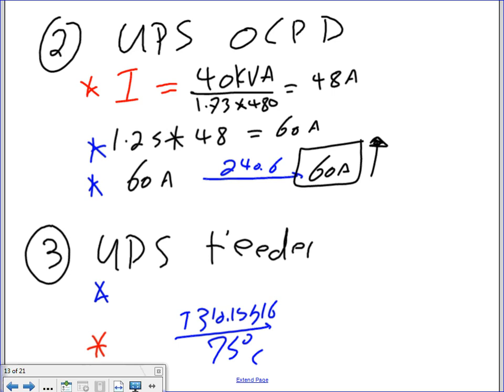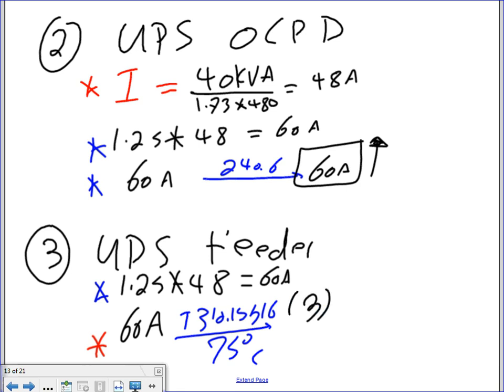Let's go to the feeder, shall we? So that's the UPS overcurrent device. Now the UPS feeder. Adam, it's identical to the overcurrent device, the same calculation, guys. You take 1.25 multiplied by the full load current, which is 48. We already did this one. End up with 60 amps. Take your 60 amps to 310.16, 75-degree column, and that will get you 3 conductors, number 6 AWG THHN.